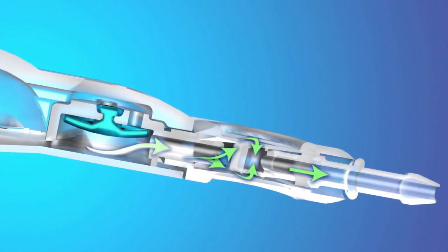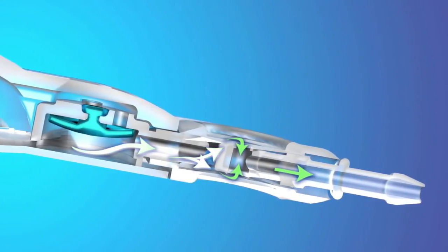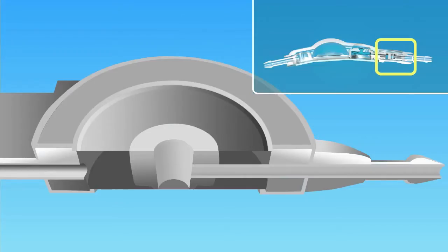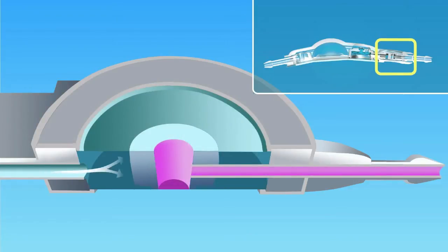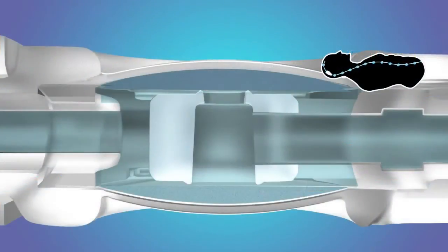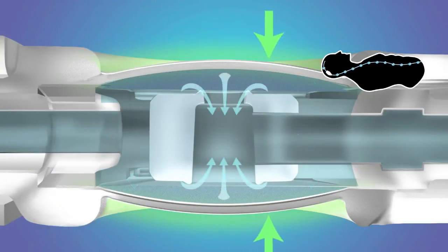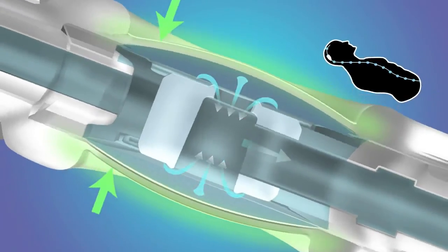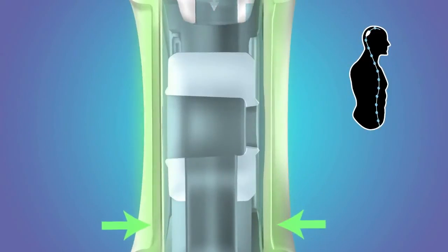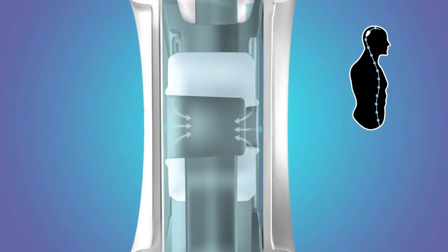After passing through the membrane valve, the CSF reaches the Delta Chamber. The inlet area of the Delta Chamber diaphragm is greater in size than the outlet drainage port, thus allowing positive inlet pressure to control the Delta Chamber while minimizing the effects of the negative hydrostatic outlet pressure. When the patient is in the supine position, the membranes on either side of the Delta Chamber are relaxed or open, allowing for CSF flow. When the patient stands up, the negative pressure pulls the membranes closed, reducing the flow of CSF.